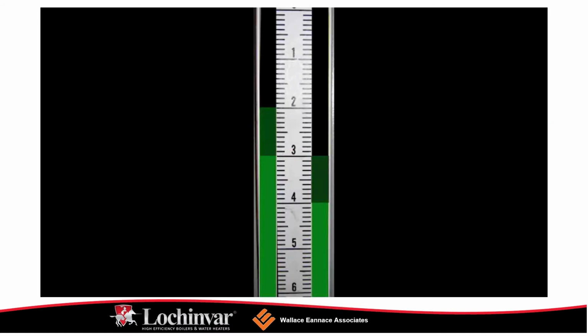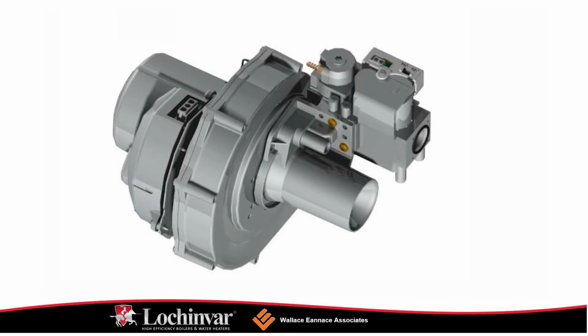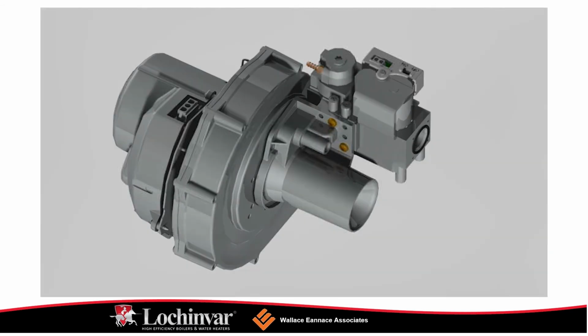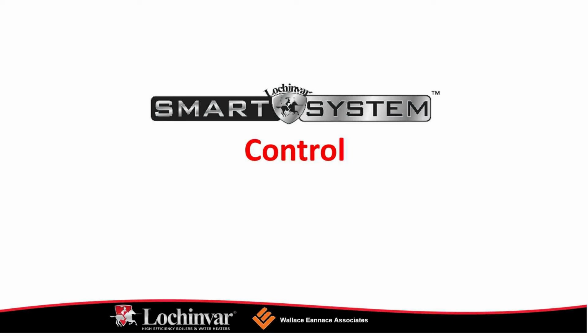Negative regulation technology is a key component in modern modulating boilers, due in large part to its safety characteristics. All negative regulation systems are made up of the same basic components. These include a negative regulation gas valve, a Venturi, and a fan. A standard combination gas valve will open when voltage is applied, allowing the regulated gas pressure to pass through. A negative regulation gas valve requires suction pressure in order to open the seats and allow the regulated gas pressure to pass through the valve.